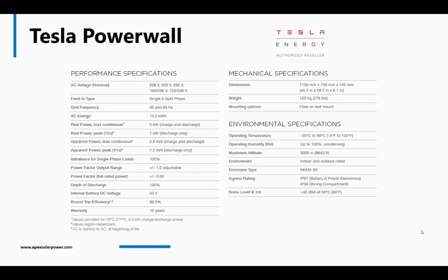The storage capacity of the Powerwall is 13.2 thousand watt hours, or 13.2 kWh. It operates at about 5,000 continuous watts - if anybody knows a 5,000 watt generator, that's the type of max continuous power the Powerwall has, with a storage capacity of 13.2 thousand watt hours. Now, 13.2 thousand watt hours sounds like a lot, and in some cases it is - it may be everything you need. The Powerwall operates at 25 amps, so anything on a single breaker in your home under 25 amps, you'll be fine with a Tesla Powerwall.